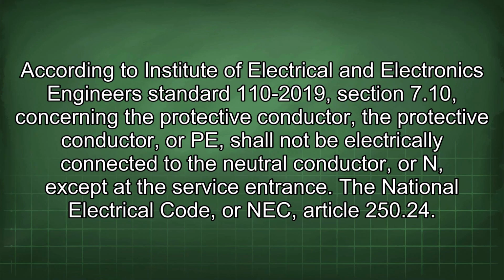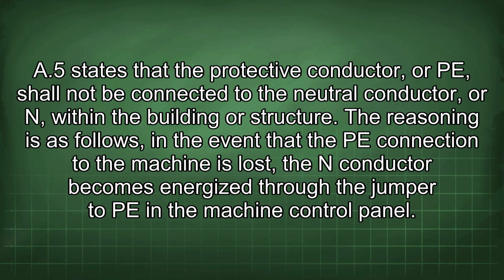According to Institute of Electrical and Electronics Engineers Standard 110-2019 Section 7.10, the protective conductor, or PE, shall not be electrically connected to the neutral conductor, or N, except at the service entrance. The National Electrical Code, or NEC, Article 250.24 A5 states that the protective conductor, or PE, shall not be connected to the neutral conductor, or N, within the building or structure.